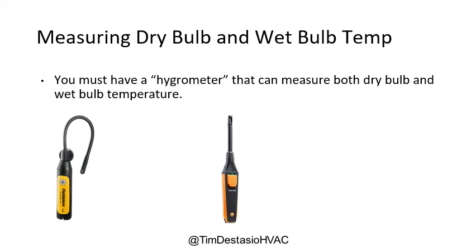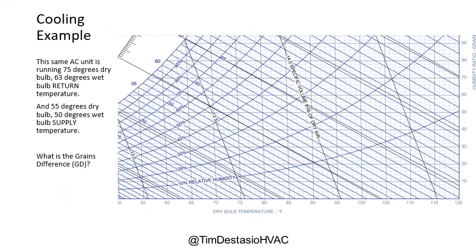You can see two examples of hygrometers that technicians use in the field — one made by Fieldpiece and another by Testo. They're very accurate and affordable. It's important to have two of them so you can take both your supply and return air readings simultaneously. With a set of hygrometers, we can plot these points on the psychrometric chart and determine the grains difference between return and supply.